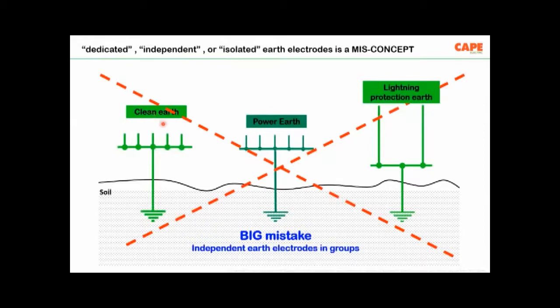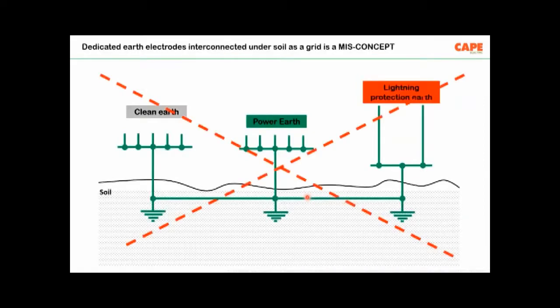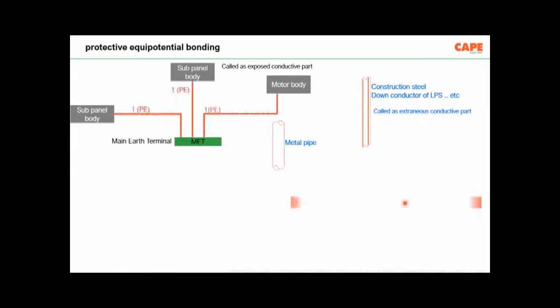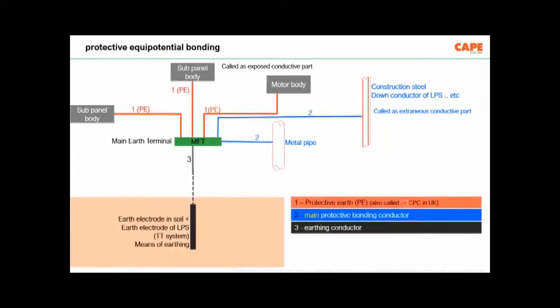Lot of buildings nowadays have this kind of earthing: clean earth, power earth, lightning protection earth, separate. This is also a big mistake. I request, please don't do it. Lot of earth electrodes, then interconnecting everything under the soil is also a wrong method. This is not the standard, or this is not technically what is recommended in the books or what is recommended in the standards and practices.